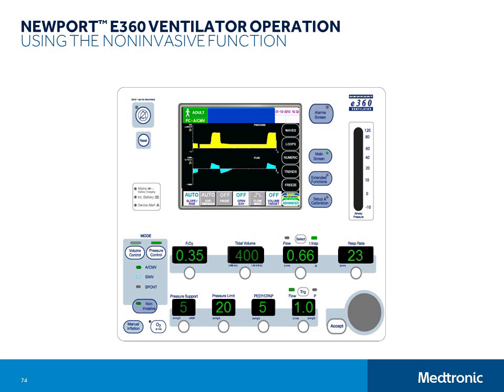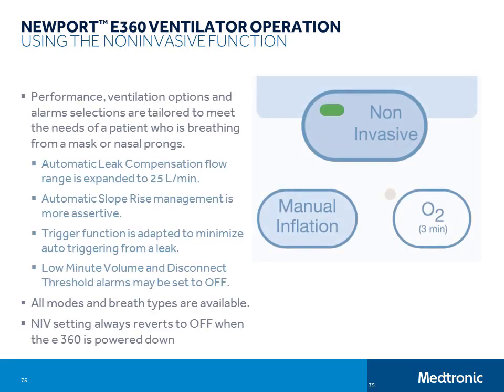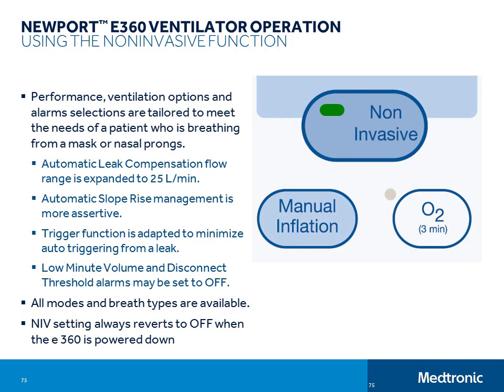The leak compensation flow range is expanded to 25 liters per minute for both the ped infant and the adult patient categories. The automatic slope rise management for all pressure-based breaths is more assertive to accommodate the higher spontaneous breathing flows of a person who is ventilated by mask. The trigger function is adapted to minimize auto-triggering from a leak, and the low minute volume alarm and disconnect threshold alarms may be set to the off position. All modes and breath types are available. The NIV setting always reverts to off when the e360 is powered down.